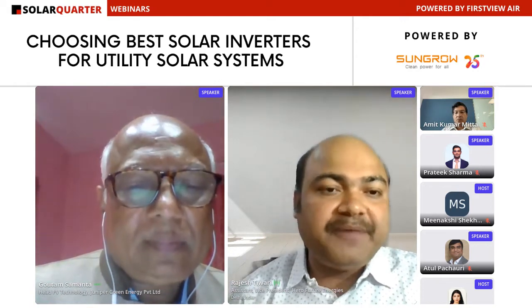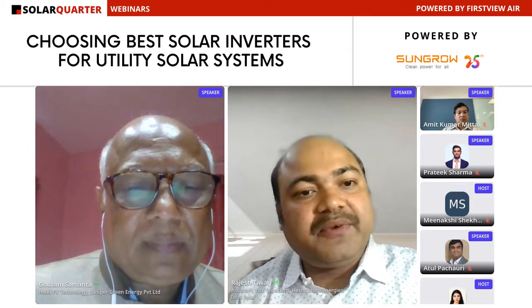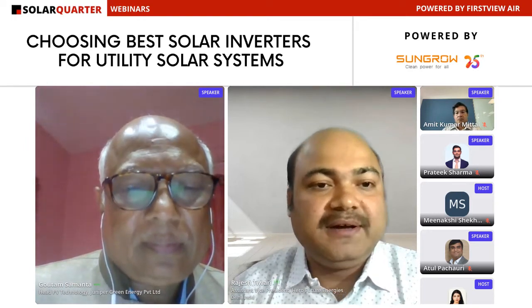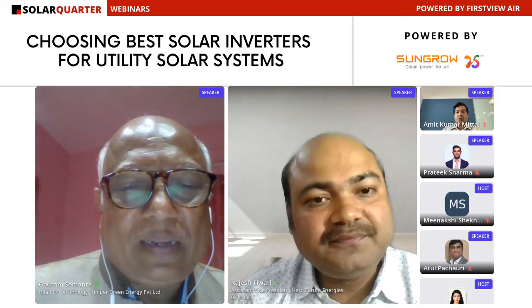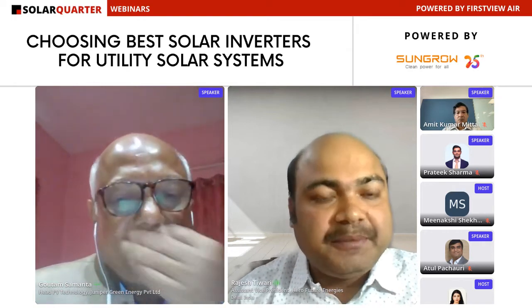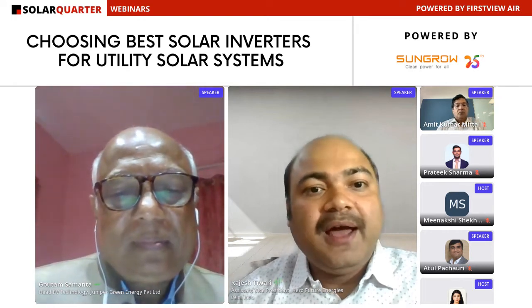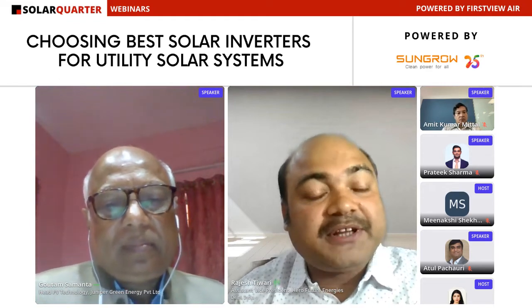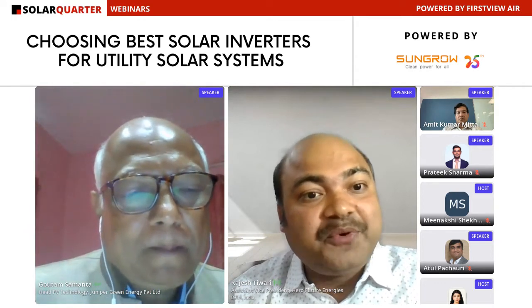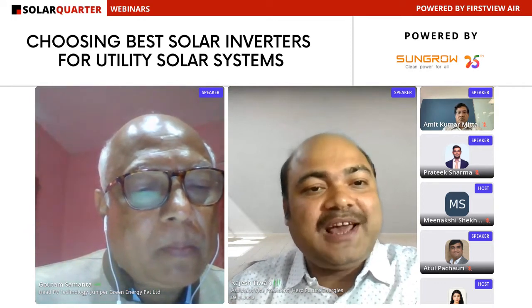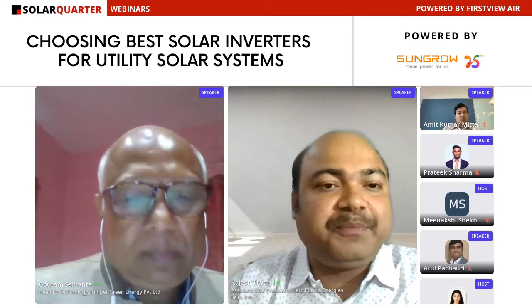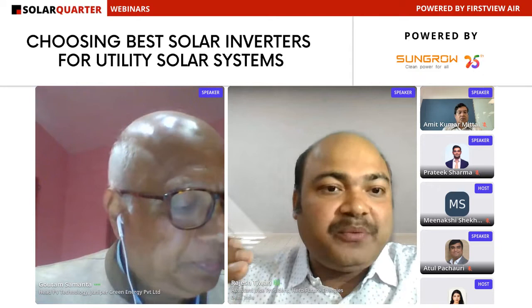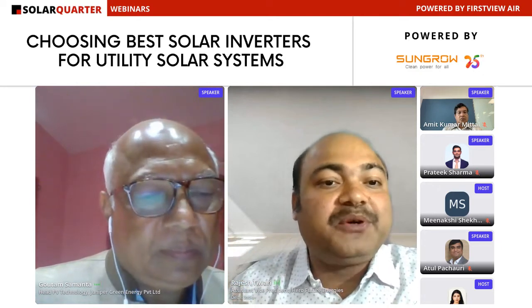So in the bifacial as well as in the tracker, in both ways, the string inverter is one of the best options. And it also minimizes the mismatch losses from the rear side for the albedo, right? Yes, due to multiple MPPTs, that is one of the best ways. And even the best part with the string inverter is that you have a higher range of MPPT voltage, starting from 500 volt to 1500 volt. In a central inverter, you will have something more than 750 volt to 1300, so a narrow band of MPPT range. So you will not be able to wake up early in the morning and run till late evening.